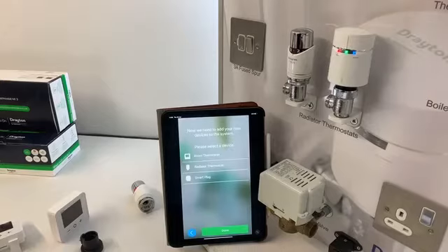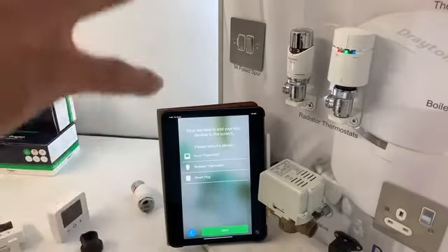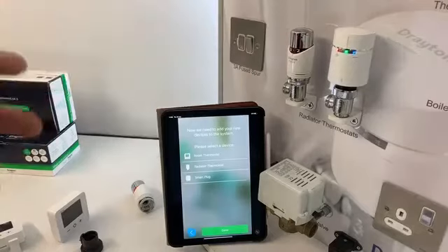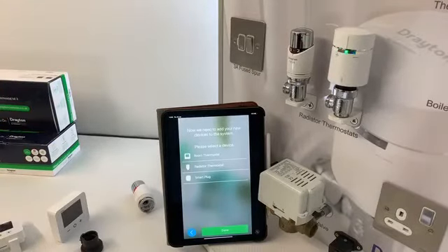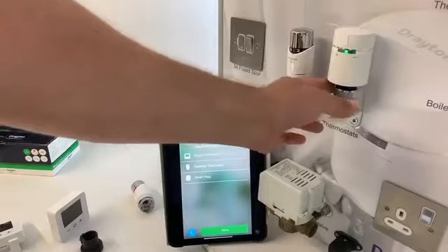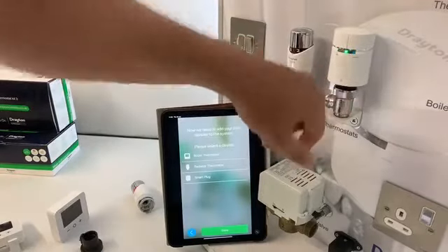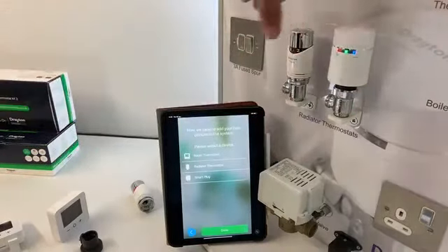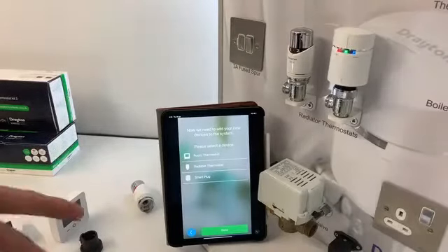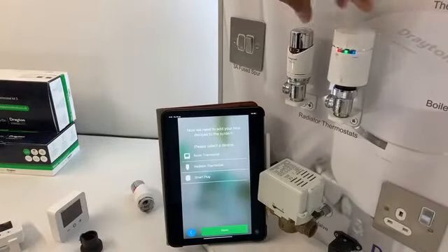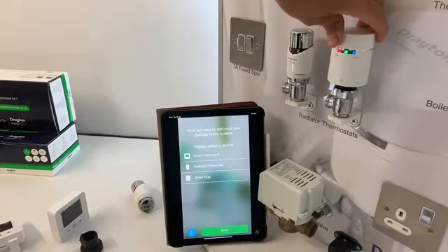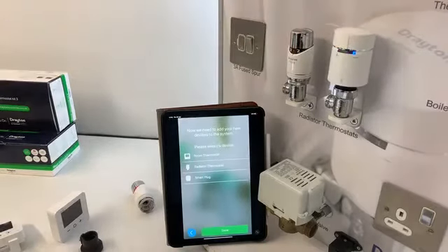Now I will go through that once more, because it's really imperative that we get the fitting to the valves correct, because that's normally where we see the biggest issues. If you've got any sort of control issues, it's normally that the head isn't tight with respect to either the body or the adapter. So I will just take you through that again. Incidentally, this one here that we've just added, we can either leave it and it will auto calibrate, or if you hold it to the minus, you can actually do the calibration. So hold to the minus until it drives down. That's now calibrating, and this is how we can adapt to various different valve bodies, and we've got such good compatibility because it will go through this auto calibration cycle.